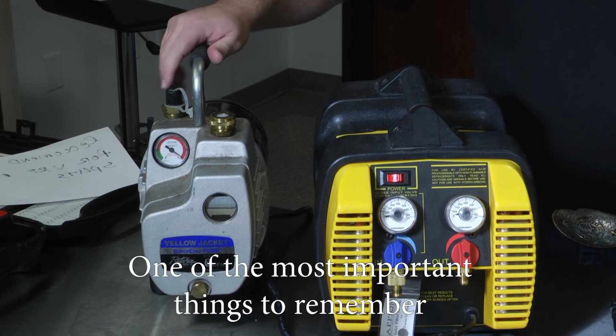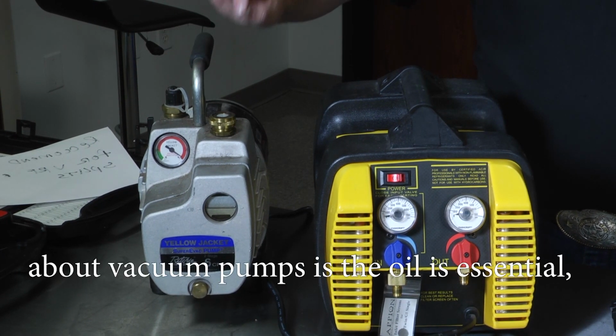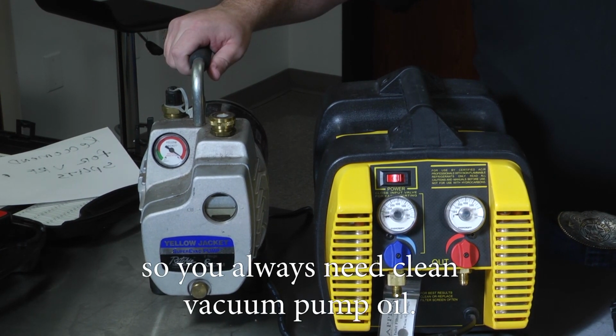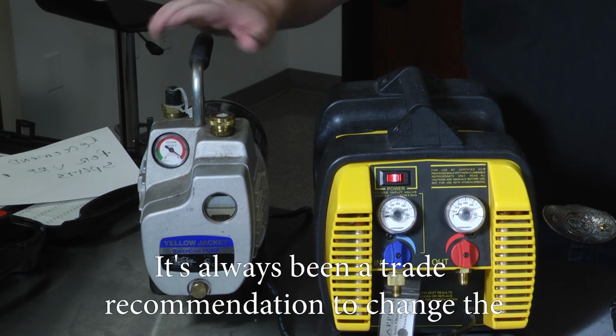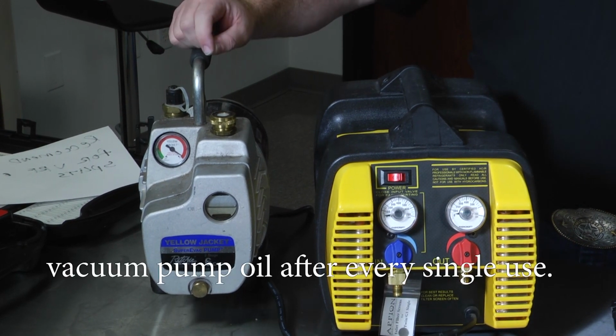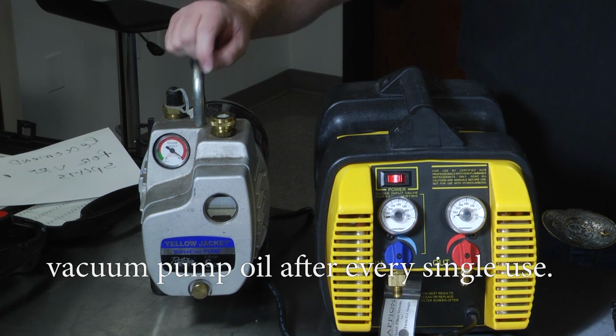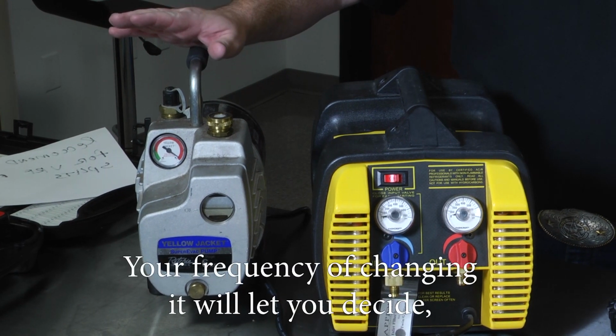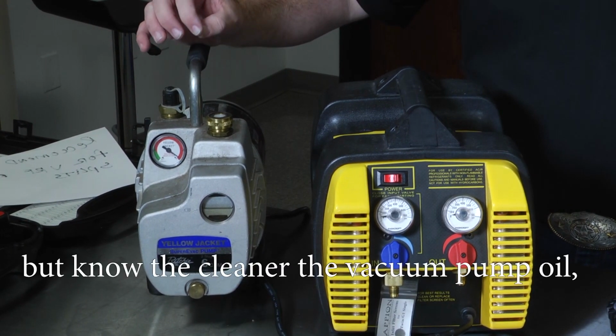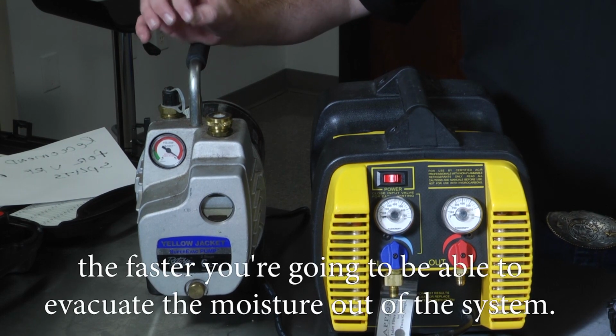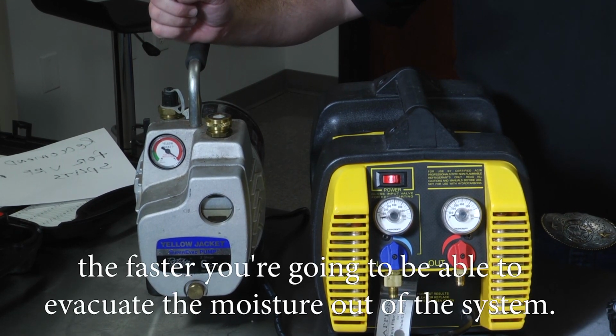One of the most important things to remember about vacuum pumps is the oil is essential, so you always need clean vacuum pump oil. It's always been a trade recommendation to change the vacuum pump oil after every single use. Your frequency of changing it will let you decide, but know the cleaner the vacuum pump oil, the faster you're going to be able to evacuate the moisture out of the system.